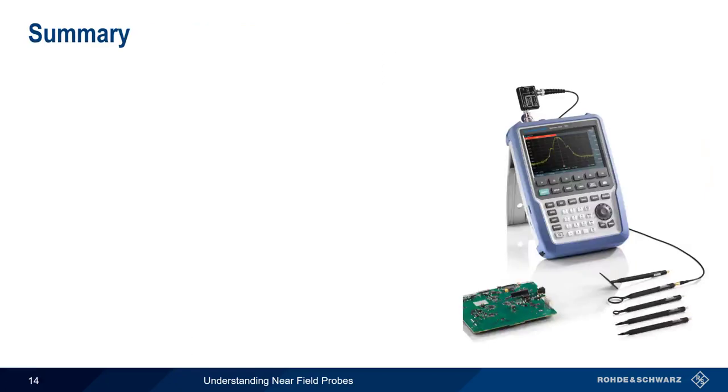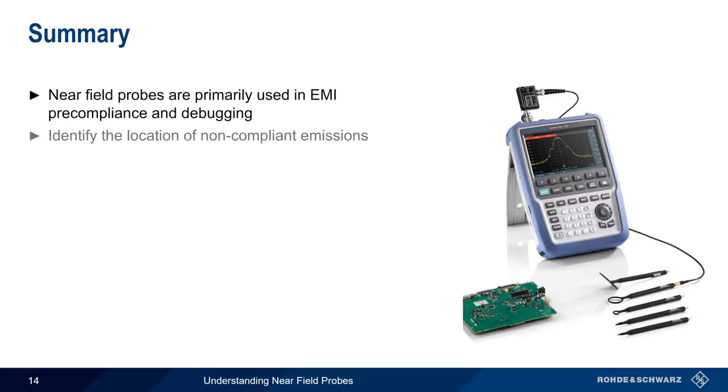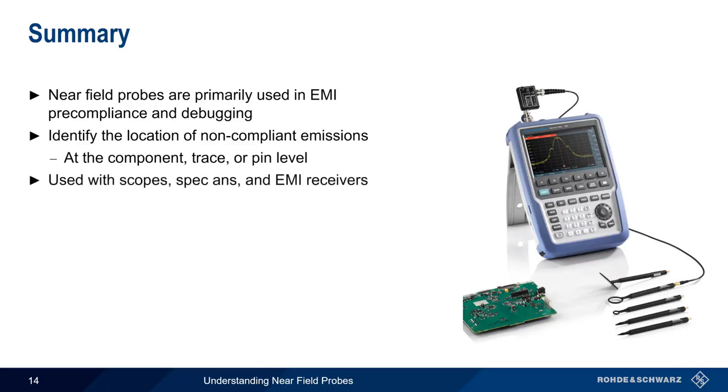Let's end with a brief summary. Near-field probes are primarily used in EMI pre-compliance and debugging, in order to detect, and then locate, non-compliant radiated emissions, typically down to the component, trace, or pin level. Near-field probes can be used with different types of instruments, such as oscilloscopes, spectrum analyzers, and EMI receivers.